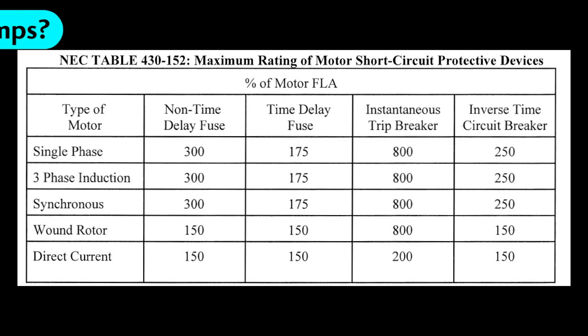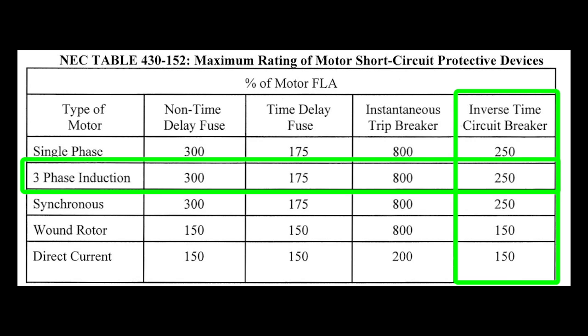Sizing a circuit breaker for use with a motor is easy. In the US, you just go to Table 430-152 of the National Electric Code and look up the answer. For motors, you want to use this inverse time breaker column which says size the breaker at 250% of the motor's full load amperage.